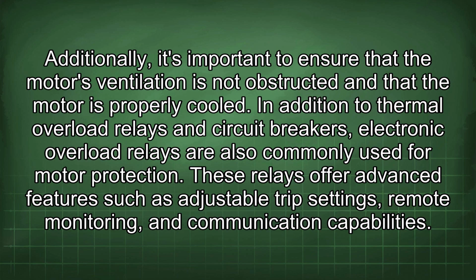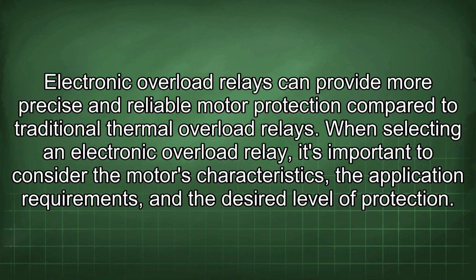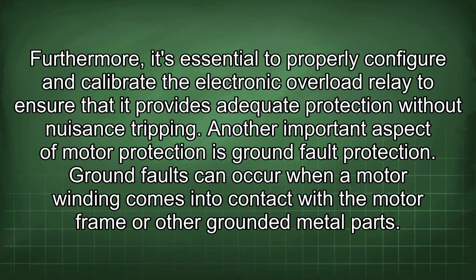In addition to thermal overload relays and circuit breakers, electronic overload relays are also commonly used for motor protection. These relays offer advanced features such as adjustable trip settings, remote monitoring, and communication capabilities. Electronic overload relays can provide more precise and reliable motor protection compared to traditional thermal overload relays. When selecting an electronic overload relay, it's important to consider the motor's characteristics, the application requirements, and the desired level of protection. Furthermore, it's essential to properly configure and calibrate the electronic overload relay to ensure that it provides adequate protection without nuisance tripping. Another important aspect of motor protection is ground fault protection.